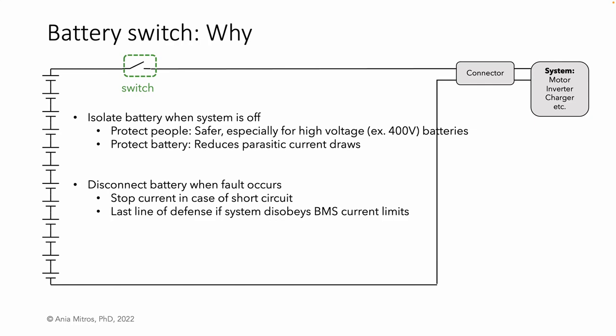The battery switch is also our last line of defense in case of certain faults. For example, a short outside the battery can pull a large current from the battery, and that current can damage the battery or the wires and connectors between them. The location of the short may get very hot, resulting in propagating damage. Opening the switch may need to be done quite fast.